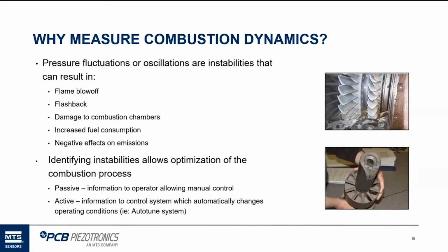So, why measure combustion dynamics? There's a lot of reasons. Most major OEMs, when they made their turbines, have done something to look at it, whether it's been mounted temporarily when they're starting up a turbine after an outage, or installed all the time. There's always been some sort of system, going way back many years. But if there are fluctuations or oscillations or instabilities, it can cause a lot of damage to a gas turbine. You get some flame blow off. There can be a flashback, like an explosion within the chamber, which in turn can cause damage to the combustion chambers.